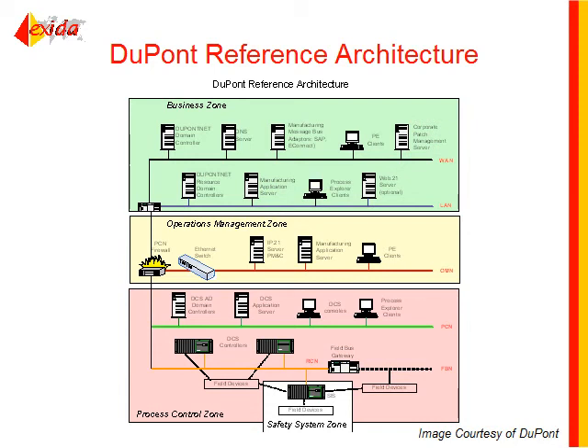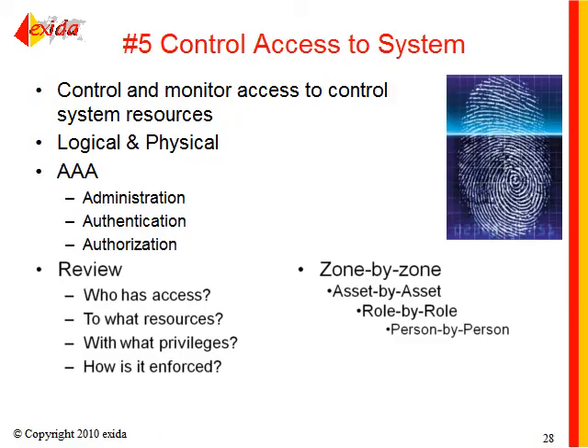Many end users have also developed their own reference architectures. One well-known one is the DuPont reference architecture, also a 4-layer type with the business or office network and the control system network separated by the operation management zone - also called the demilitarized zone. The purpose is to make sure systems on the business network do not have direct access to the control system network. They have to request information through a server in the operation management zone, and likewise control system components cannot talk directly to the business network - they must communicate through the DMZ. Also notable is the dedicated zone or subzone for the safety system within the process control zone.